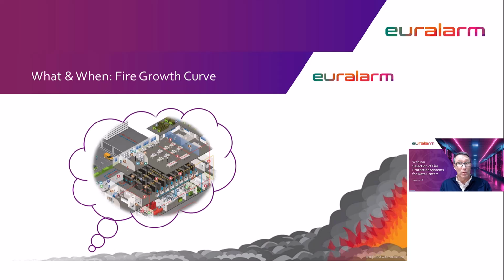Let's flip this now and we'll move from the white space to the grey space, to a diesel generator where a hose could burst and the resulting fuel be sprayed on a hot manifold. There's likely to be instantaneous heat, flames and fire, and loads of it, no incipient stage.